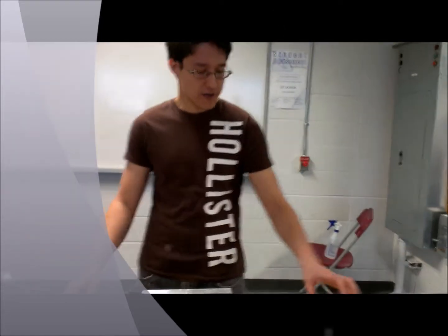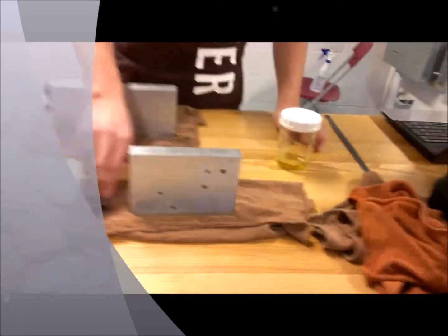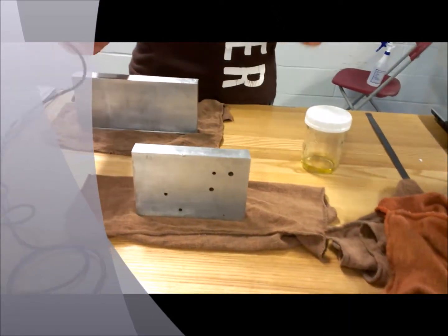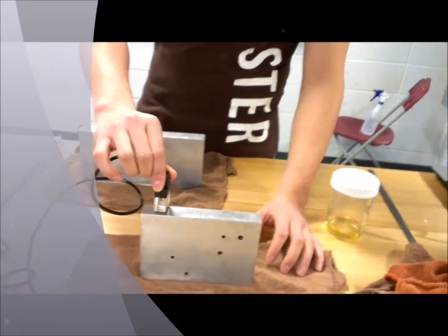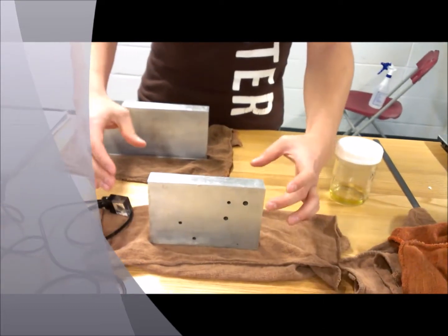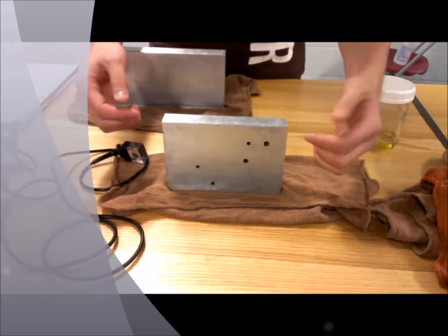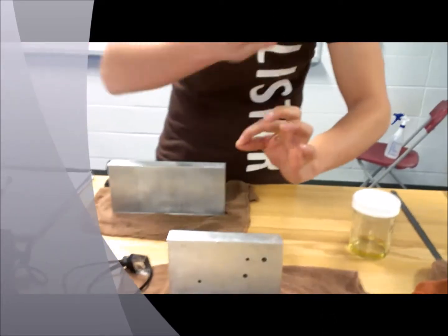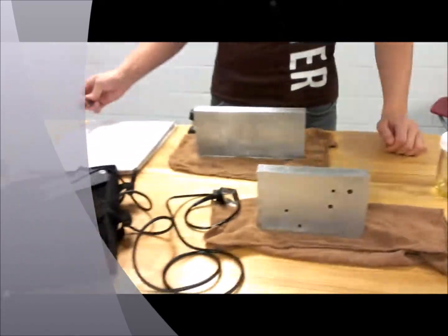For this procedure, we're using olive oil as a lubricant. You take some and put it on the block of whatever you're testing, and this probe is also lubricated and passed over all these holes. You'll notice that these holes are really easy to see. We're just going to use this as an example. Holes in real life can even align like so, and you really have to use your head and figure out where one starts and where one ends.